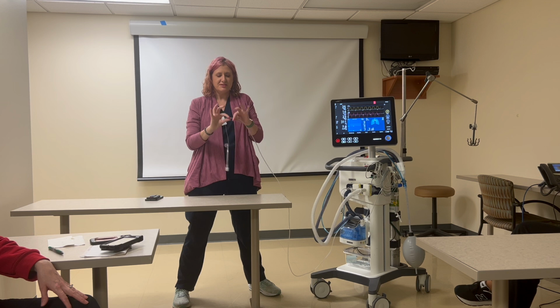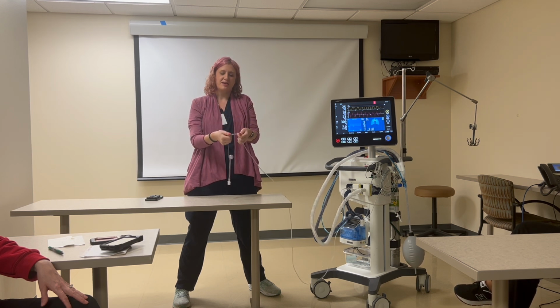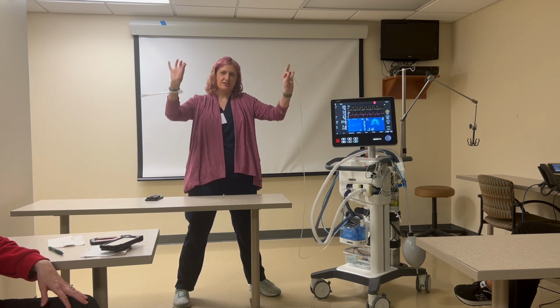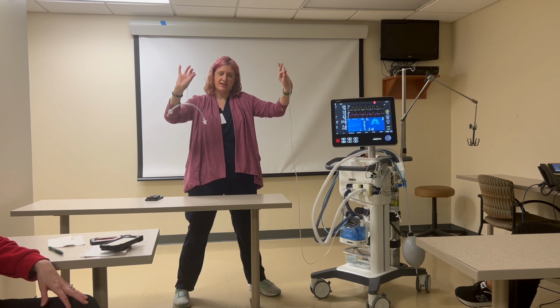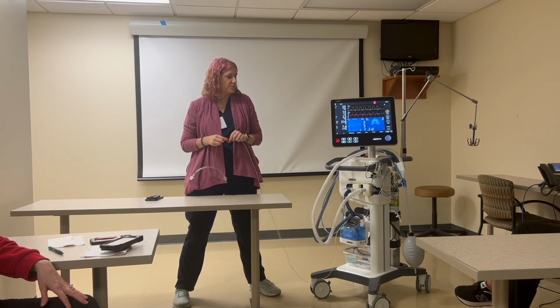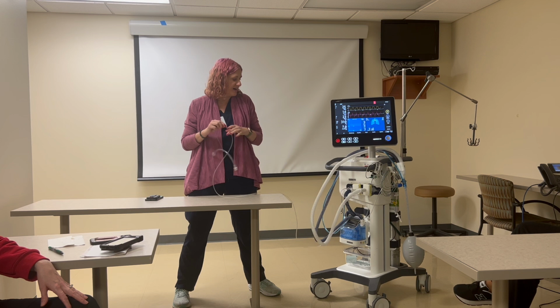So if you guys notice that this is tangled, or if you don't want to deal with it while you're getting your patient out of bed, just like a Chinese finger trap, you're gonna push it in and twist for it to come off just like this. Gives you about 20 seconds before it's going to alarm cuff leak, so you can untangle it and then just simply reconnect, and it's going to apply the same cuff pressure.